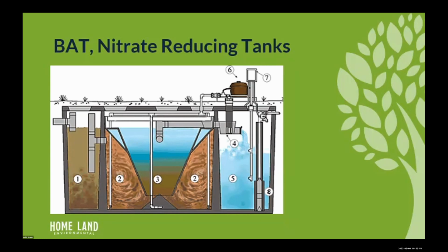We got oxygen. Well, this bacteria loves to eat just like septic bacteria. So we got the food here, we got the oxygen. It's a little bit more high maintenance, this aerobic bacteria. It doesn't like to swim around. It needs to sit and hold somewhere. So these tanks, when they first started doing it, they just weren't getting the reaction because there wasn't enough of the bacteria. There wasn't a high enough count of bacteria because there's not enough surface area in that tank for them to live in. So the next step is we got to develop some type of media we can throw in this middle chamber to let the bacteria have a home.